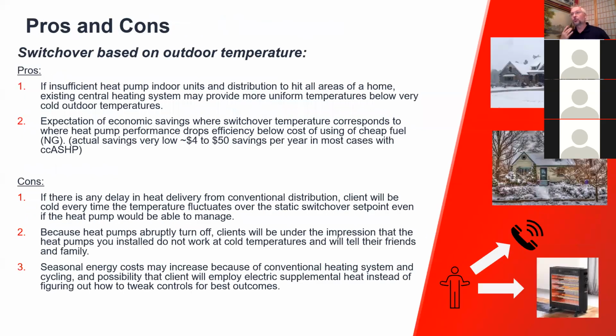So pros and cons. Switch over based on outdoor temperature. This is one of those things where if you've got a house where you don't have complete coverage by the heat pump zones, the only reasonable way may be to say, once I get below a certain temperature, the ballooning out of warm air from centrally sourced ducted heat pumps is insufficient to overcome the force of cooling that may happen on extremities of the house. And that's where we would need to say, okay, below this temperature, we need to switch over and use a conventional heating system because of the distribution challenges going on there.